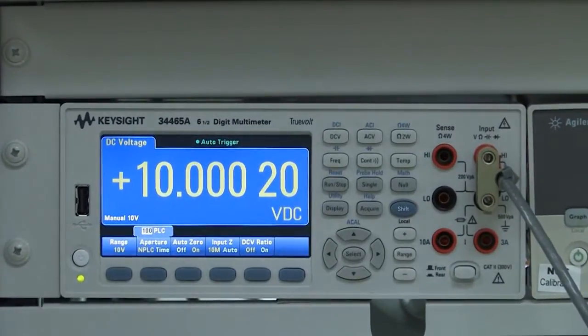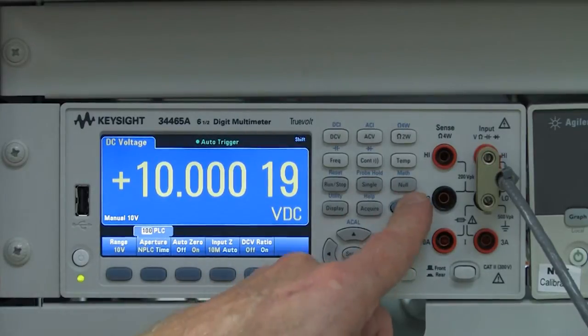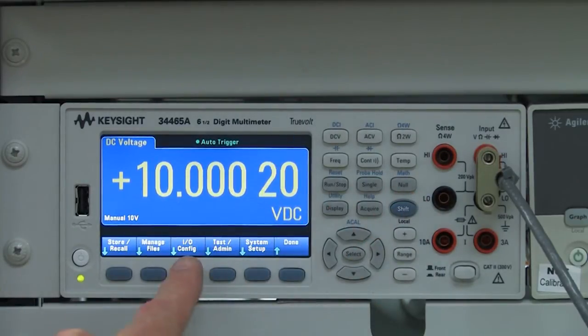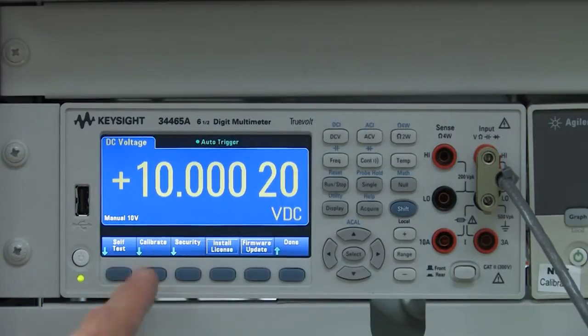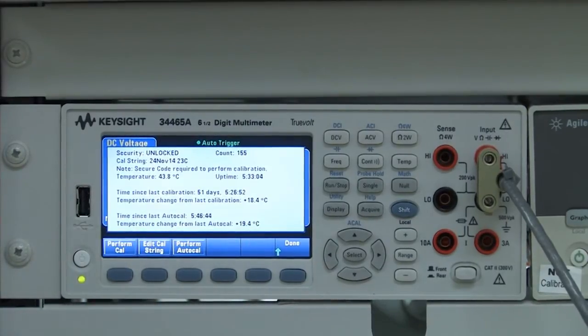Earlier in the video, I had started an auto calibration by pressing the shift followed by the up arrow key. You can also activate the auto calibration by pressing shift, utility, test admin, calibrate.